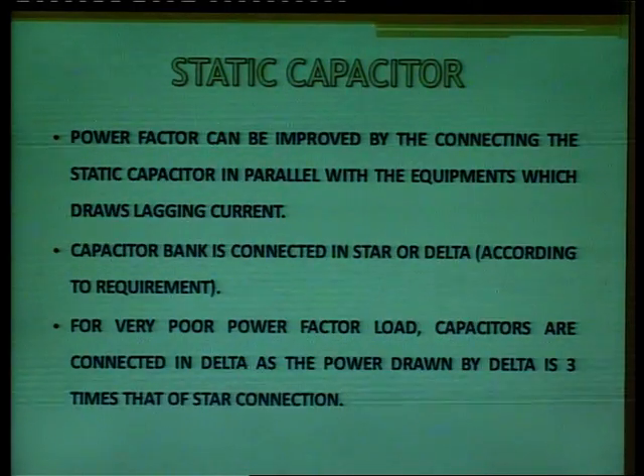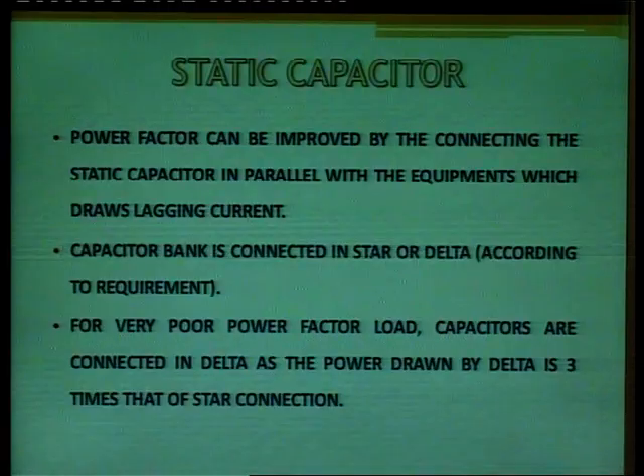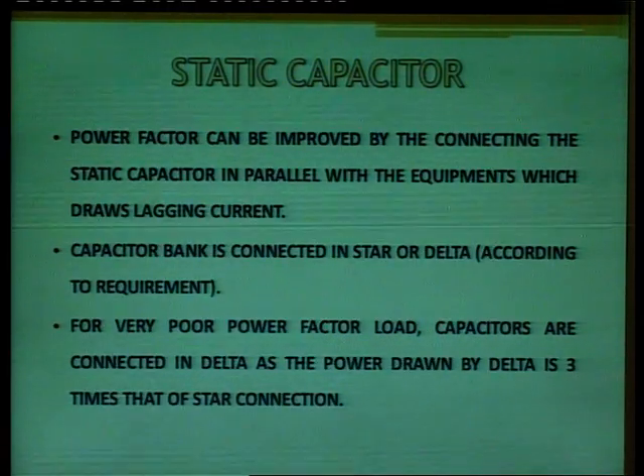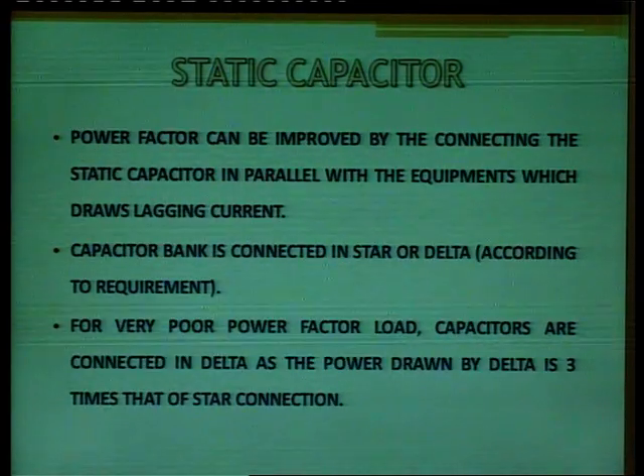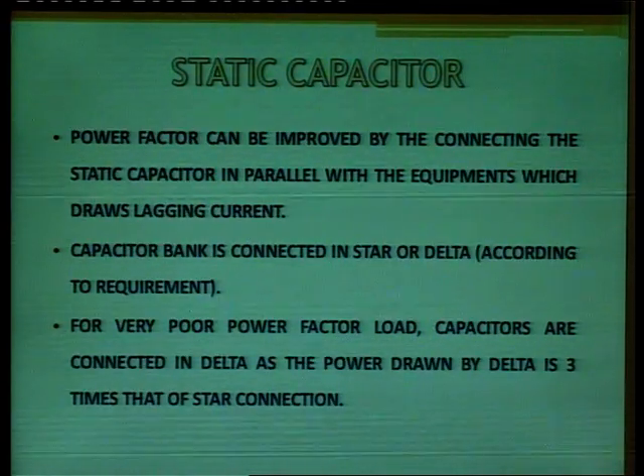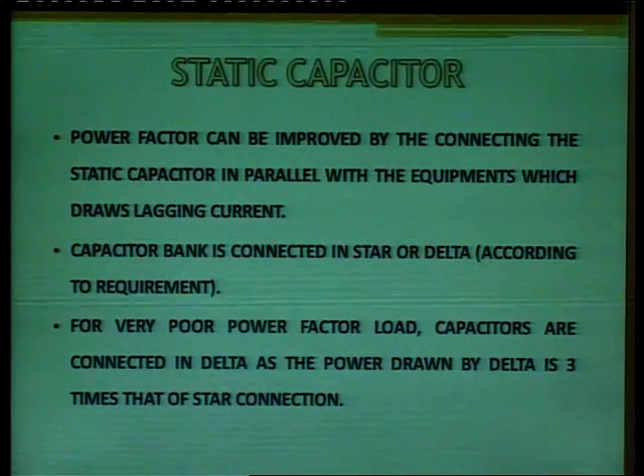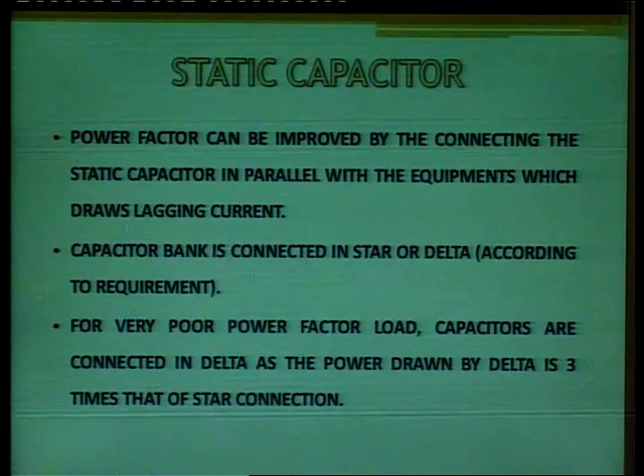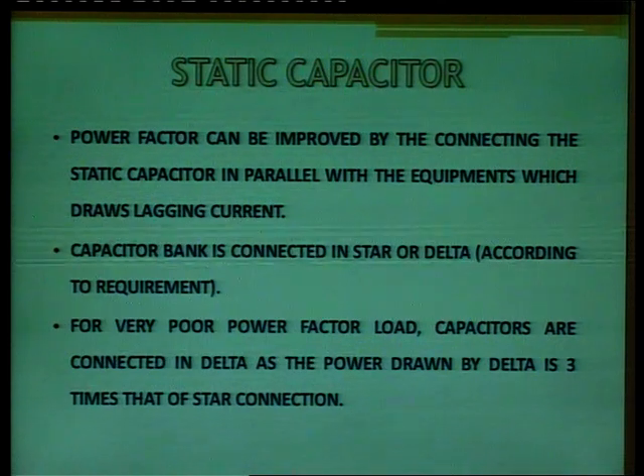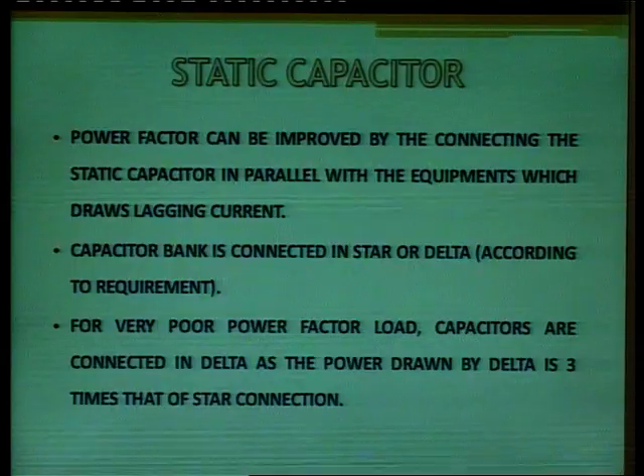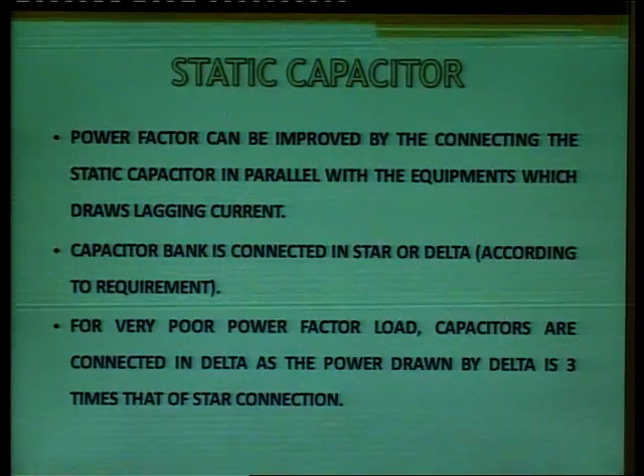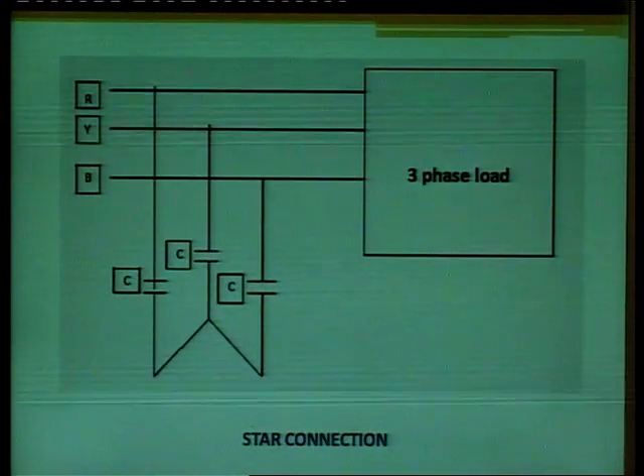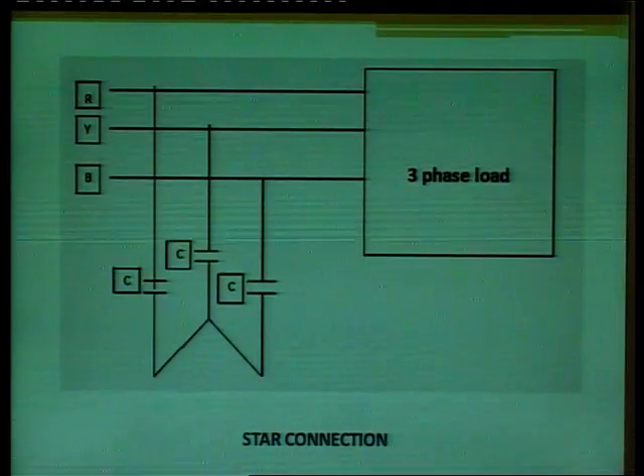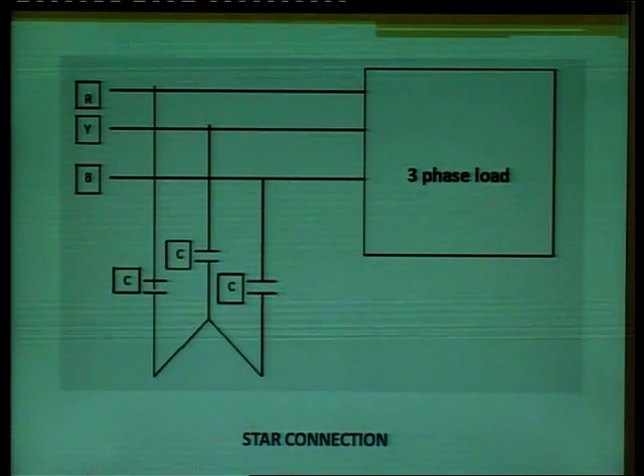So a capacitor bank is connected in star or delta. You can see in powerhouses and substations that capacitor banks are installed. These capacitors are connected in star or delta. For a very poor power factor load, capacitors are connected in delta, as power drawn by the delta is 3 times that of the star connection. So these are the connections. You see we have a 3 phase load, red, yellow, blue.